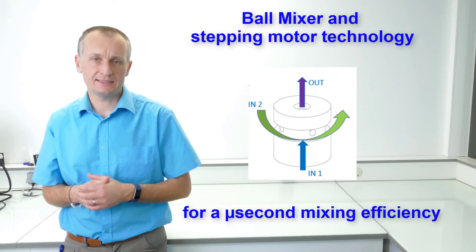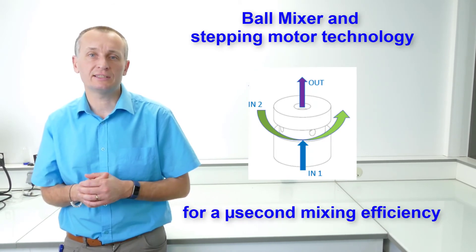This performance is not only due to the cuvette small volume, but to the mixing and the pushing technology, as the mixing process must be completed much faster than the dead time.